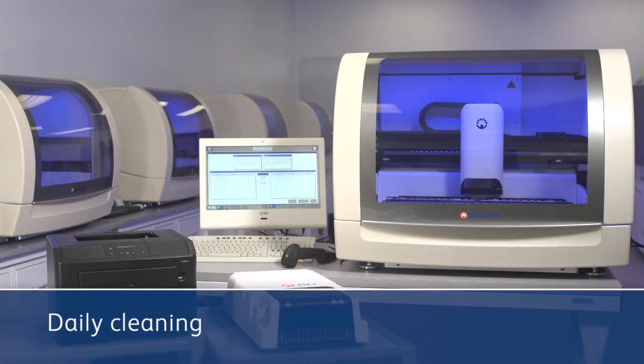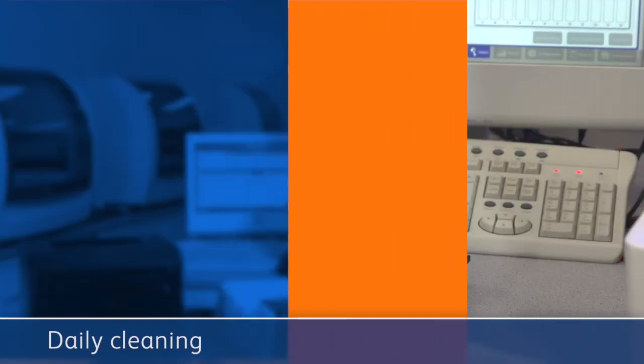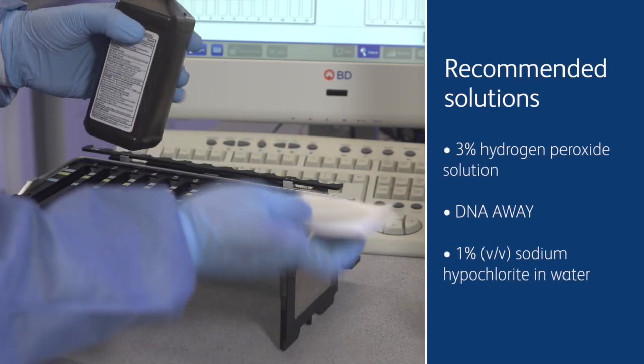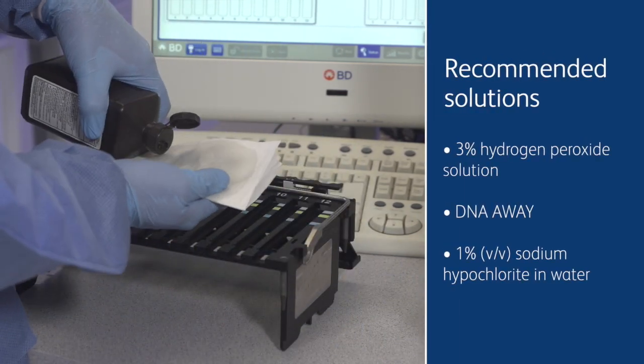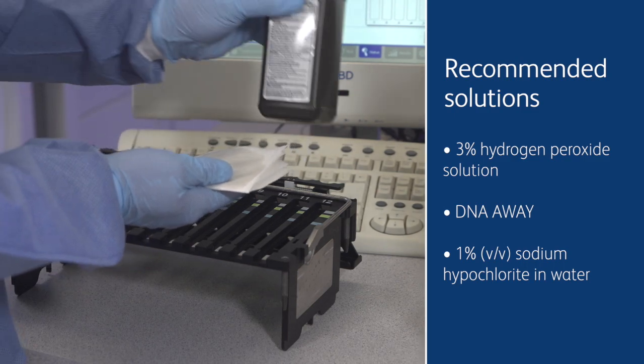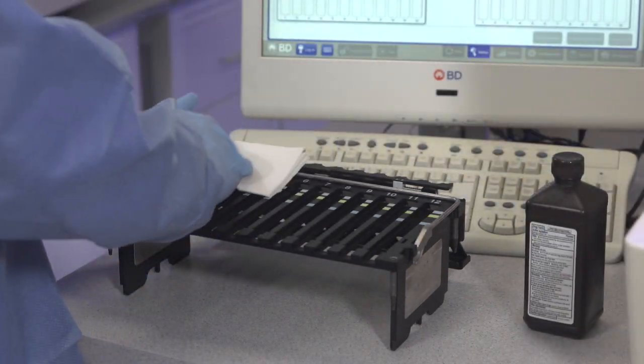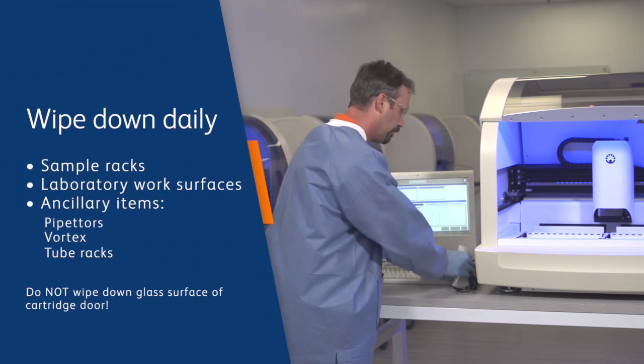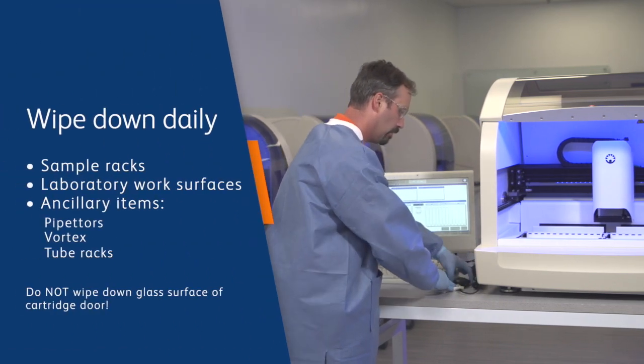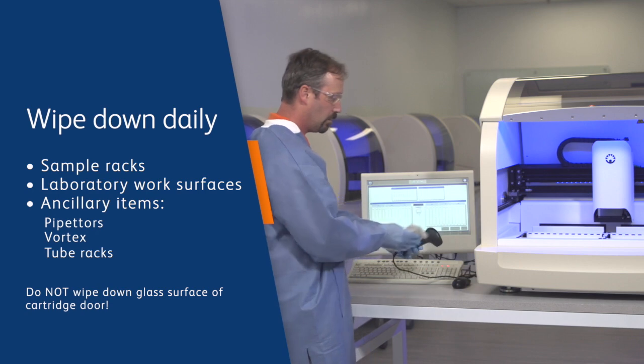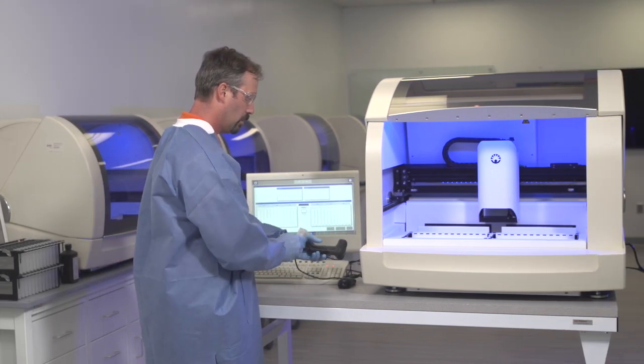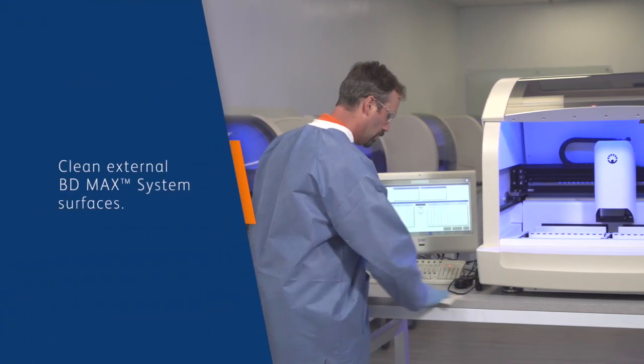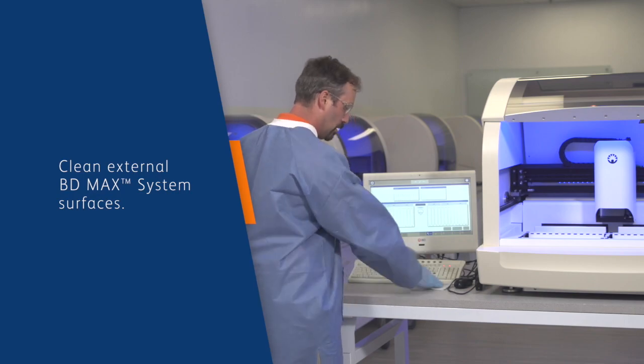First, let's go over the procedures you should follow every day. Dampen a lint-free cloth with the recommended solution. Use it to wipe down the sample racks, laboratory work surfaces, and ancillary items such as pipetters, vortex, tube racks, etc. It is recommended that you clean external BD Max system surfaces before the internal surfaces.